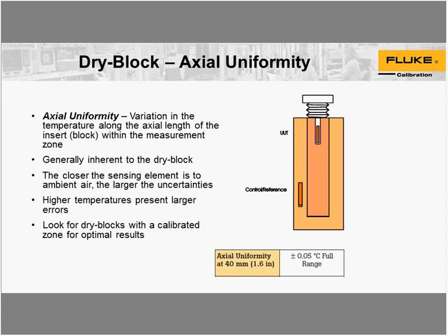What this means, not at that particular point, but it's referencing full immersion up 1.6 inches, is we're going to have a good zone of plus or minus 0.05. Things to consider in your applications, again, especially if you've got a lot of short sensors to be tested.